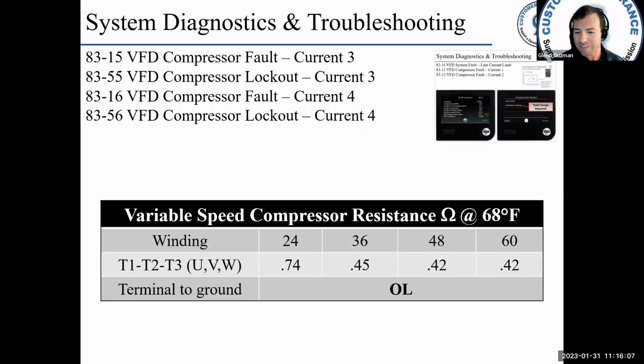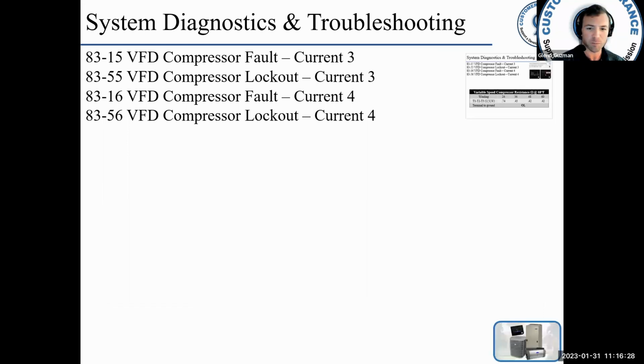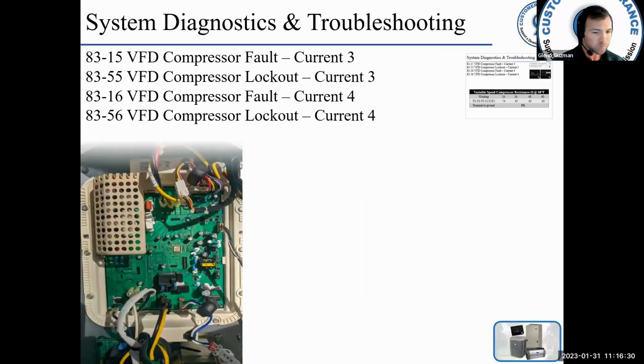Check the compressor resistance. You can see the resistances are at 68 degrees. So if you're above or below that, there could be a little bit of variance. Obviously we should have OL to ground. If we're reading 0.42 to ground, it's a dead short. So check your compressor resistances.